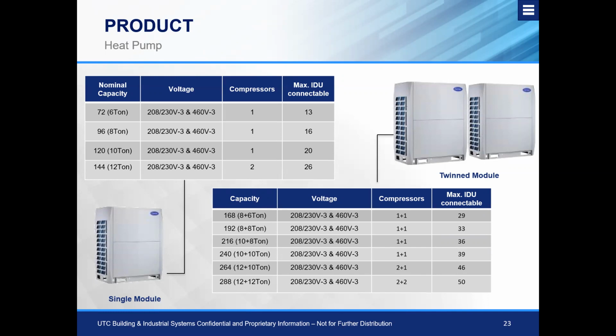Now, as we step up between our 168,000 BTU or our 14-ton unit, all the way up to our 288,000 BTU or 24-ton unit, you'll see we have a different configuration of compressors. So we see we have 2 compressors all the way up until we reach 22 tons of capacity. Then we start adding 3 compressors on that 22-ton system. And on the 24-ton system, we have 4 compressors. And again, the maximum number of indoor units that we can connect on that twin module does raise as well. And you'll see twin modules, more coil surface area, more compressors, better low ambient heating performance.